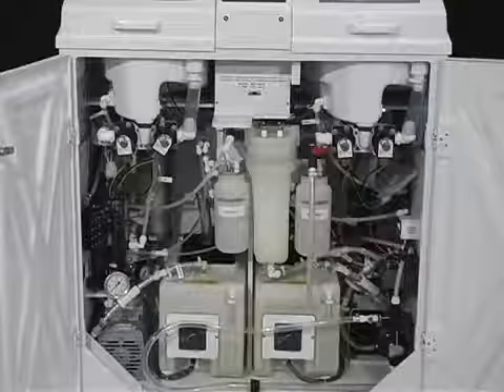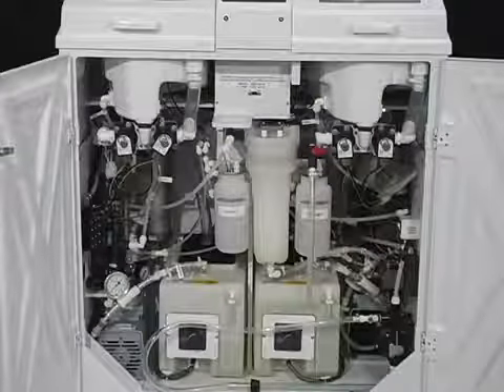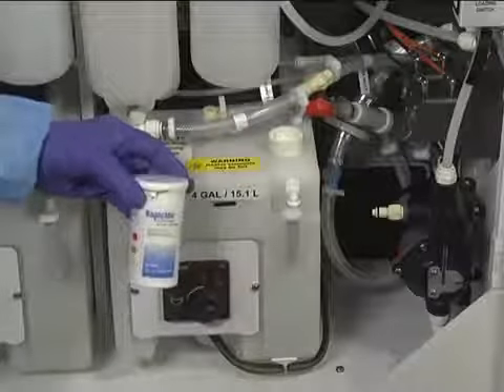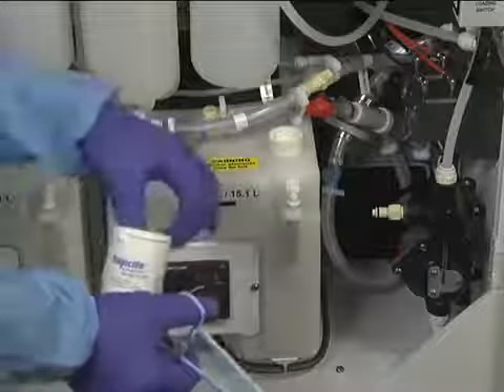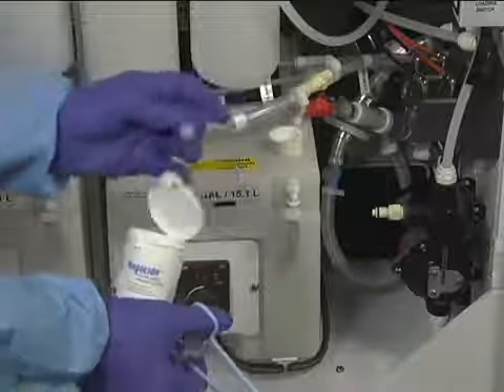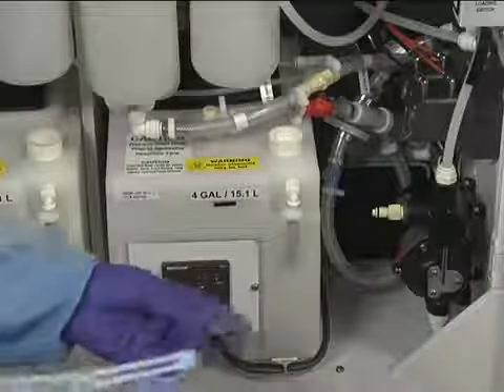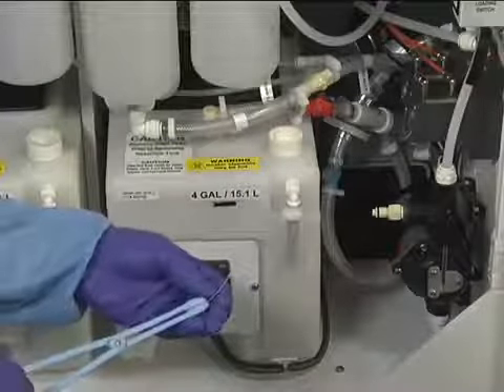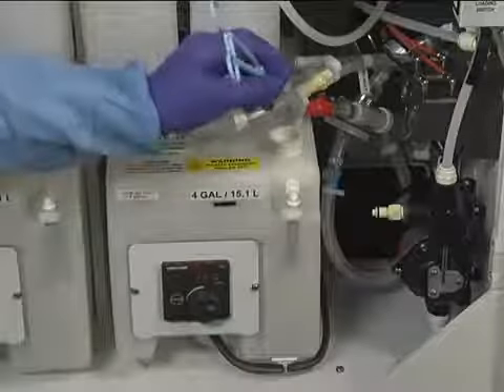Open the doors to inspect the fluid levels and filters. Check the disinfectant concentration. Insert a test strip into the reservoir through the opening in the reservoir. Replace the disinfectant if the minimum effective concentration is below the directions for use requirements.